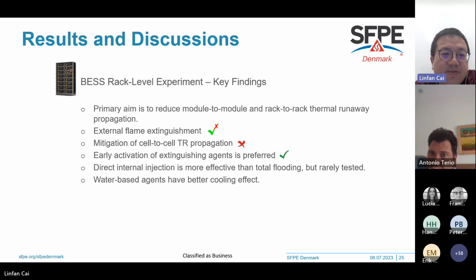So to prevent cell-to-cell thermal runaway propagation is basically not possible. So external fire extinguishment is not fully effective; only a few selected agents can do the job. For instance, high pressure water mist, Novec, and inert gases were able to put out the external flame. In terms of mitigating cell-to-cell thermal runaway propagation, as explained earlier, it is not quite possible.